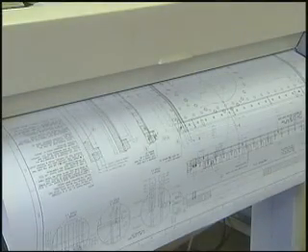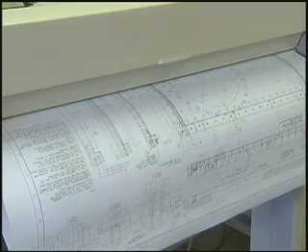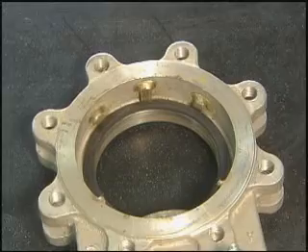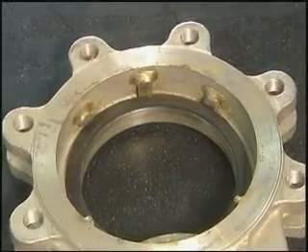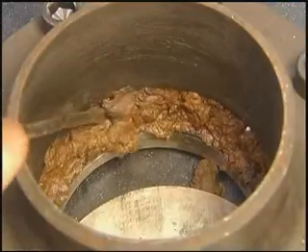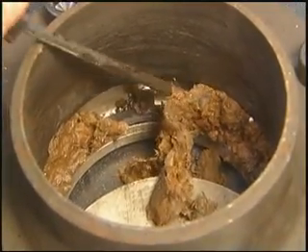Delta Industrial's superior valve design solves the significant leakage problems of the traditional knife gate valve caused by media solids. Traditional knife gate valves rely on a deep cavity at the bottom of the port which the gate must fully enter in order to seat. This deep cavity routinely fills up with flow media solids that prevent the gate from seating.